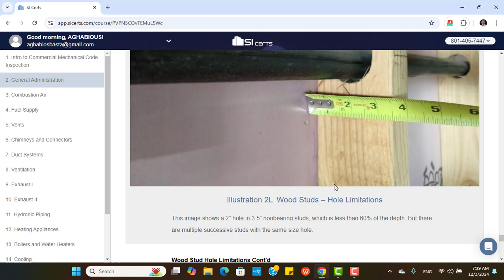Wood stud hole limitation, continued. Exterior or bearing partition studs can accept holes, but they must be less than 40% of the stud depth. Non-bearing studs can take holes less than 60% of the stud depth, whereas each stud is doubled, but holes cannot be located in 2 successive studs. Fast facts: holes in wood studs must be located at least 5/8 inch away from the edge of the stud.